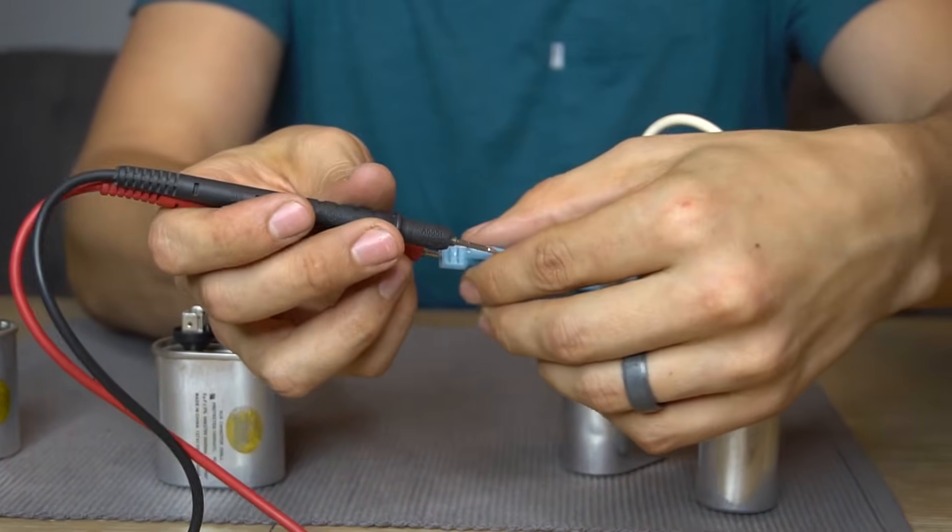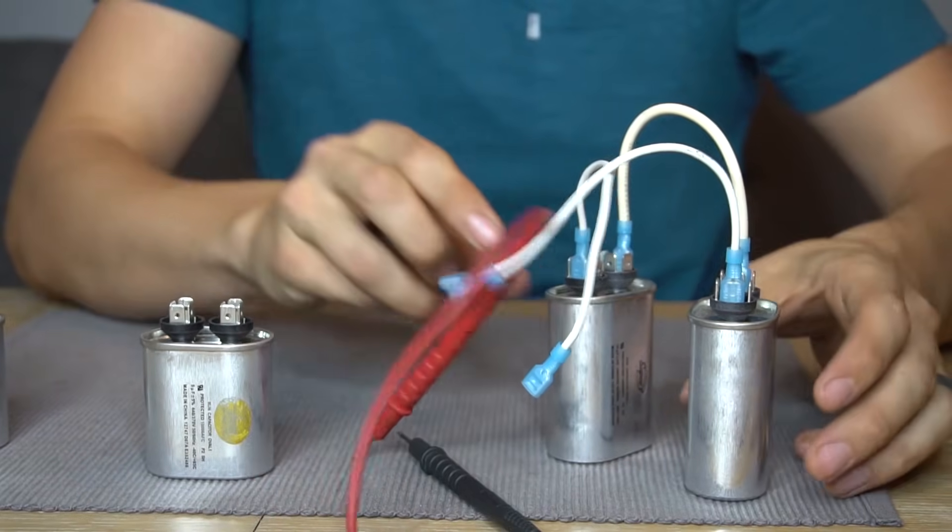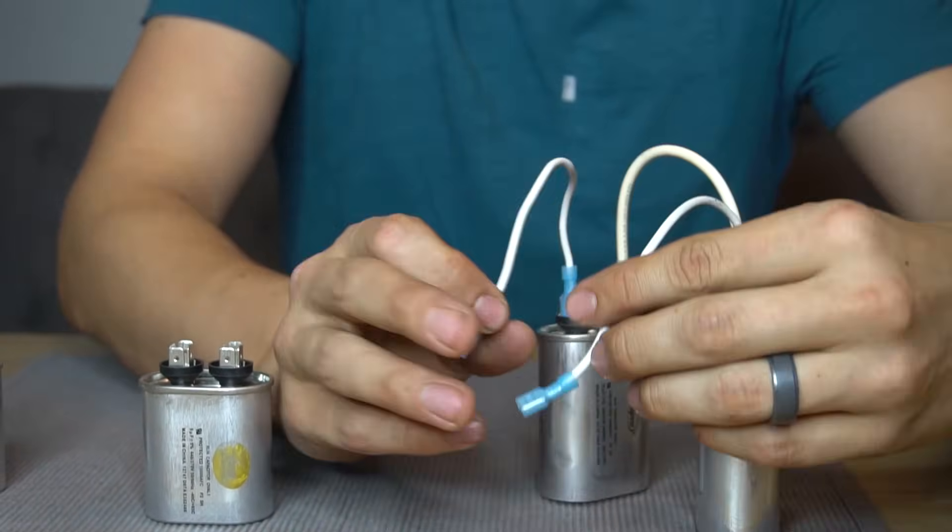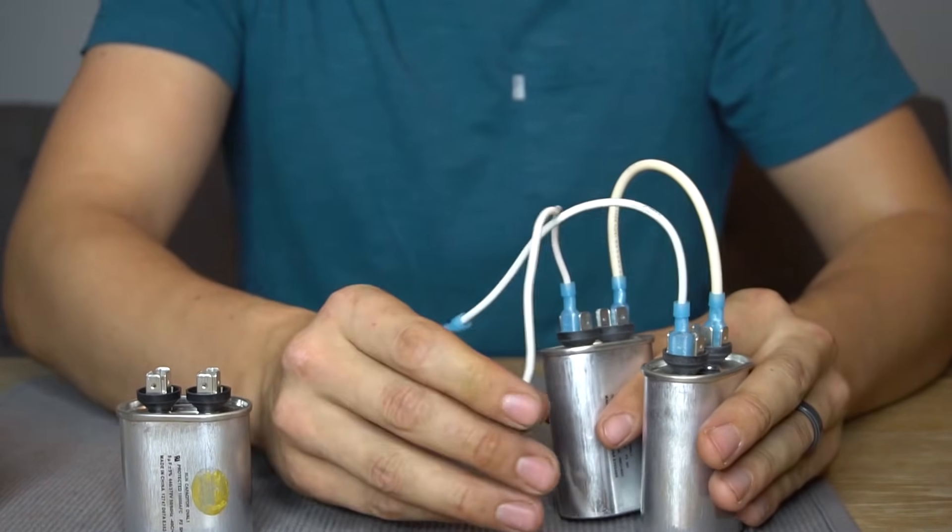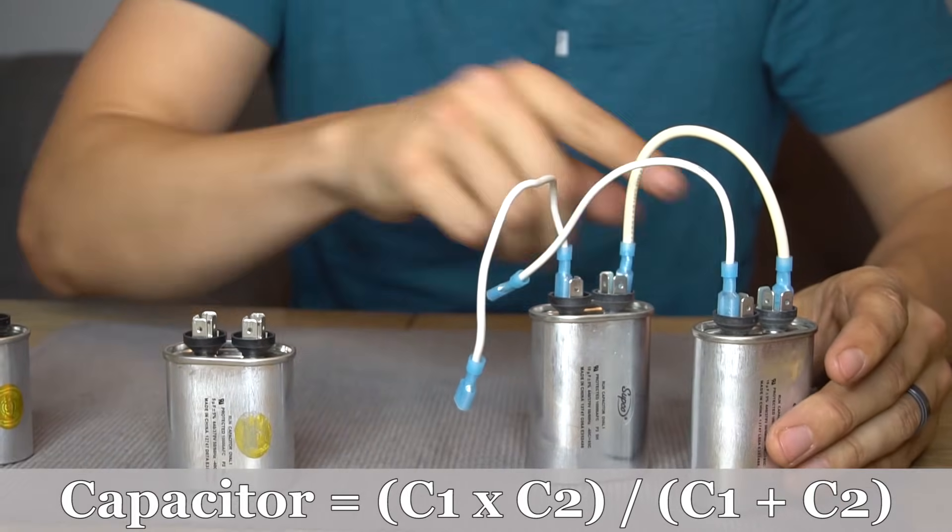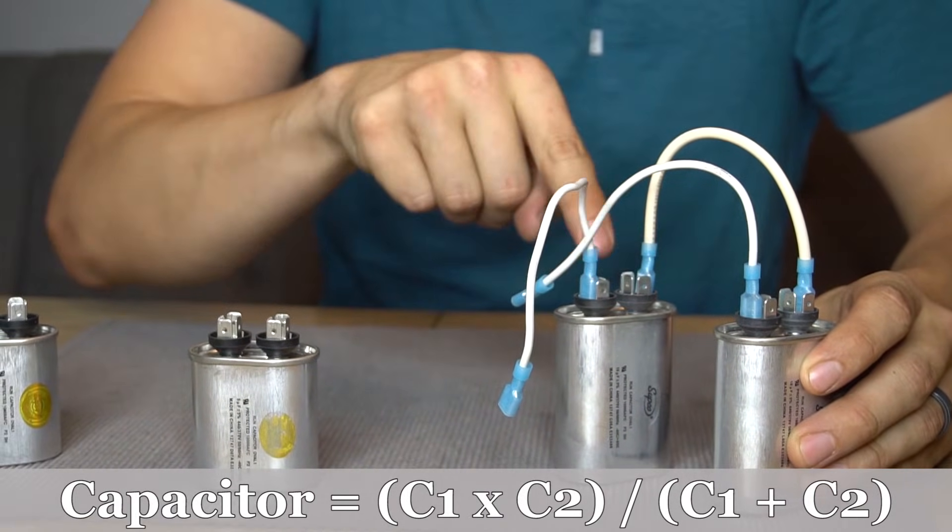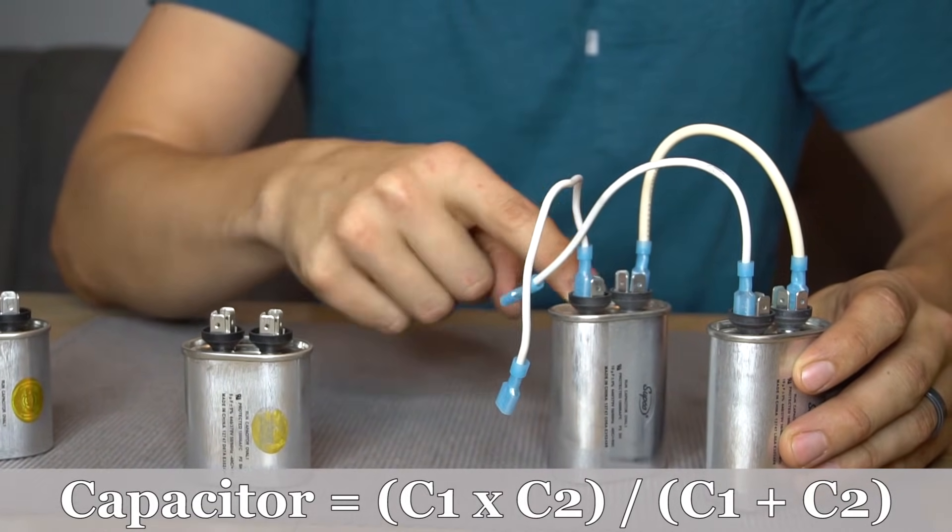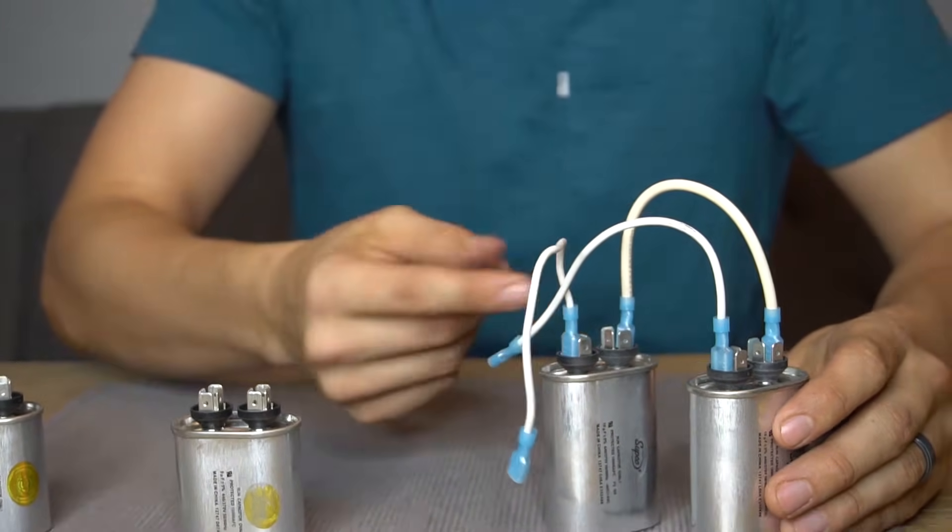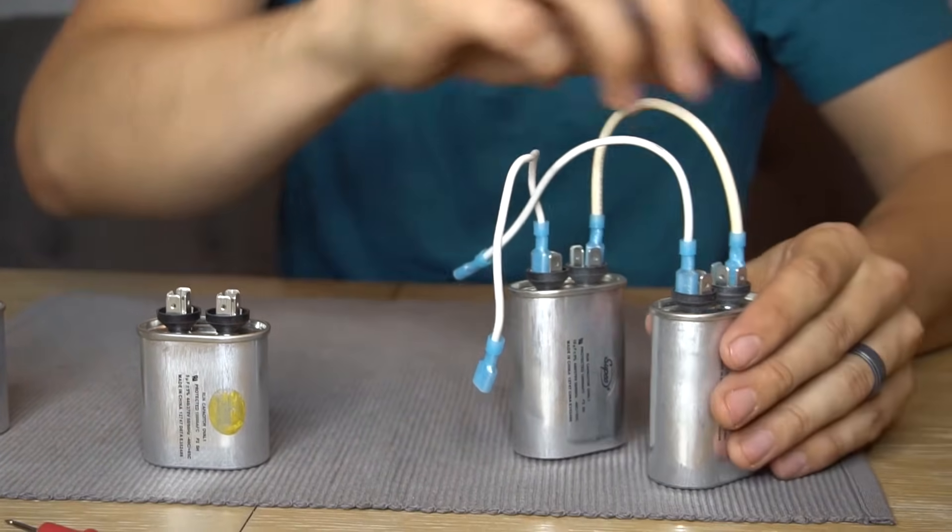So if you're wondering how that works, to figure out the end result, what the end microfarad rating will be from combining two capacitors, you actually have to use a formula. And that formula is capacitor one times capacitor two divided by capacitor one plus capacitor two. Or you could just try a couple different combinations to see what you get.